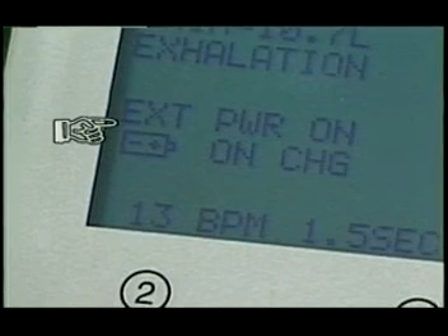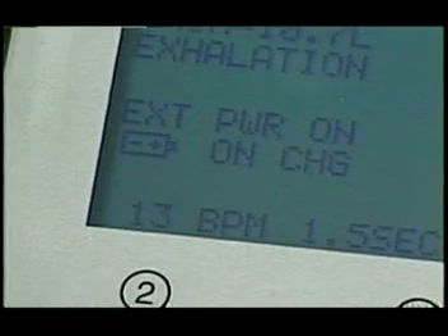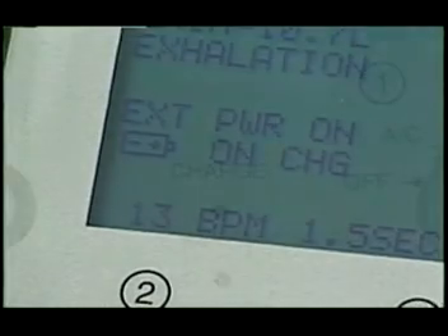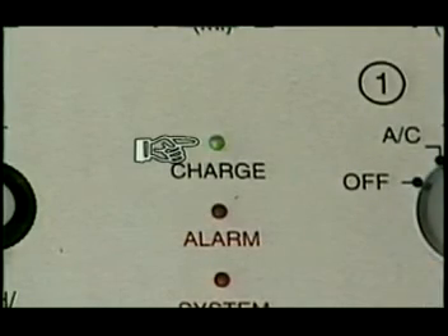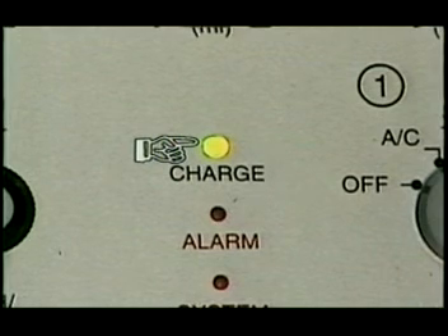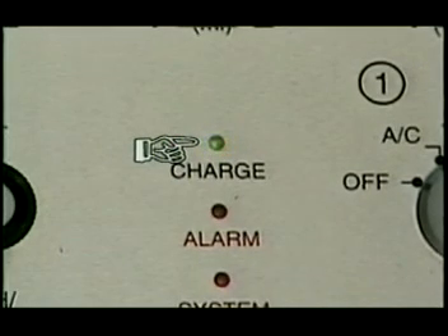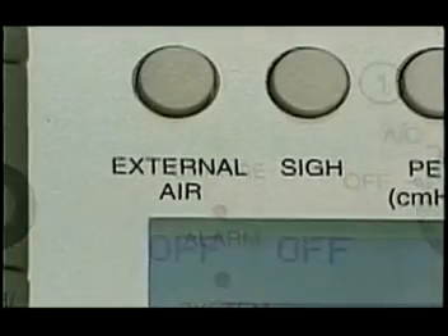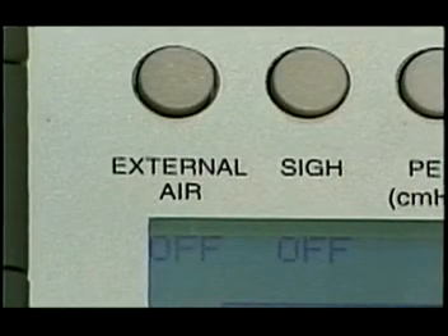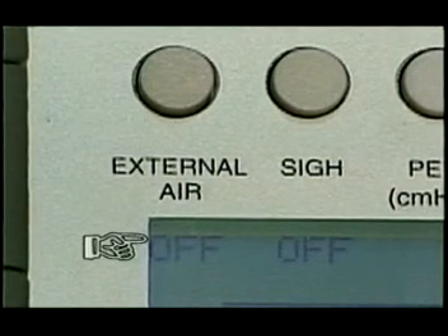The Power Information Center is a two-line area that displays the current status of external power, internal power, and fuses. If the ventilator is not connected to an external power source, the EXT PWR line is blank. The charge indicator, a green LED, illuminates when battery recharging current is flowing and turns off when the internal battery has fully charged. The external air off-on push-button switch is used with a nominal 50 psi compressed air source. Its default value is off, and its current status is displayed in the LCD beneath this push-button switch.